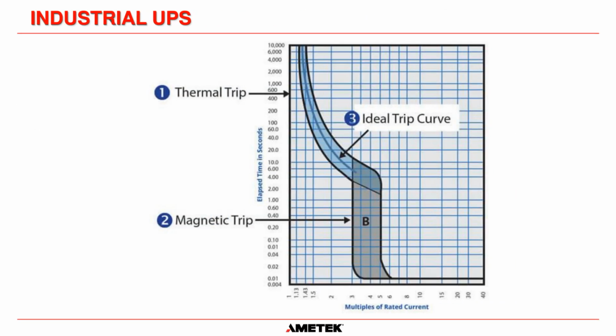And that's important when you look at the fault current tripping capabilities of some circuit breakers that are out there. Okay, so this table here shows you time on this axis and multiples of rated current on this axis. So let's say this is a 10 amp breaker. Okay, it's saying that 3 times the rated current isn't going to trip until about 3 seconds. So you're going to have 3 seconds before that breaker trips.